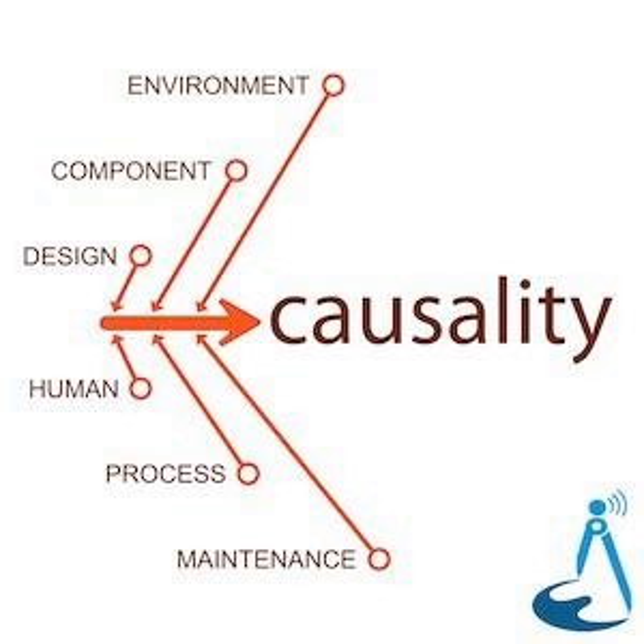But it's not all positives. Zircaloy also reacts with water, and at high temperatures with steam. The oxidation of zirconium by water releases hydrogen gas as a byproduct. Once it passes about 400 degrees Celsius, the oxidation rate increases dramatically. That increased rate of hydrogen release, in an enclosed vessel like this, will increase the pressure. As pressure increases, that further drives the oxidation process at an even faster rate. So essentially, higher temperature leads to higher pressure, which leads to a higher oxidation rate, which increases the pressure further, in a feedback loop.